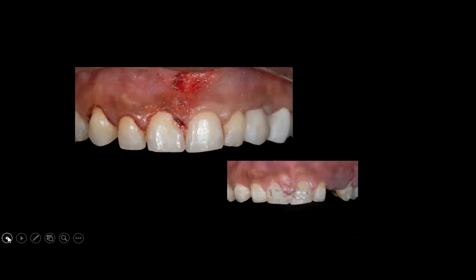Now, this step can be done with the help of an articulating paper or a cork paper. Some laser devices will provide you with a cork paper to initiate the tip. And if they do not provide you, you can use the blue articulating paper to initiate the tip. Keep the laser at a very low power setting of 0.5 to 1 watt. Touch the tip around 8 times to your articulating paper.